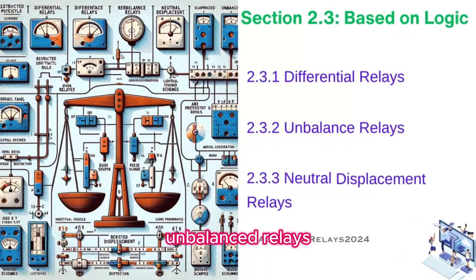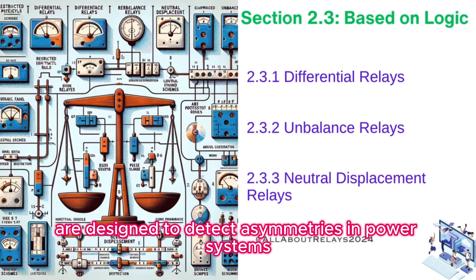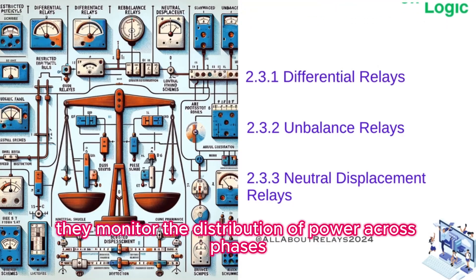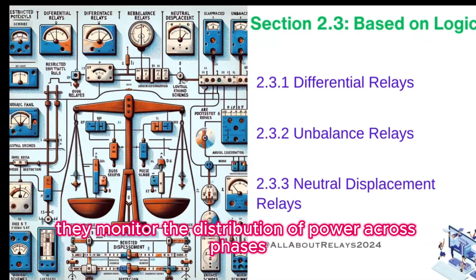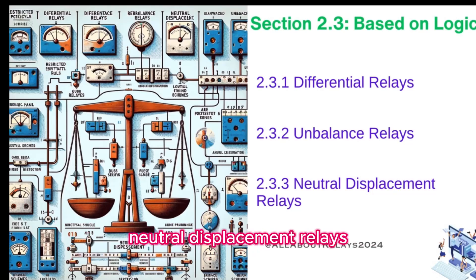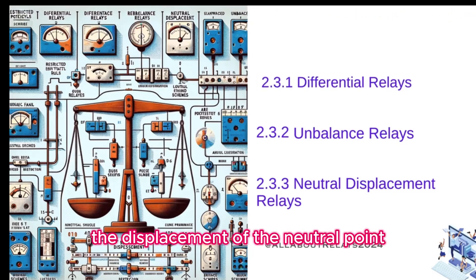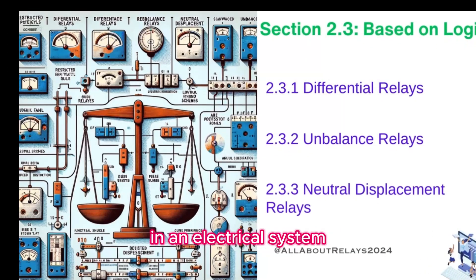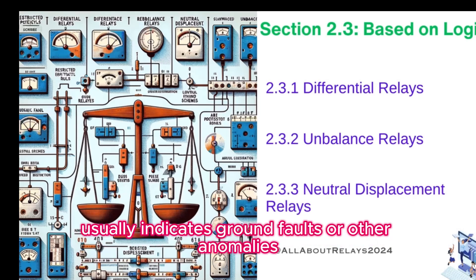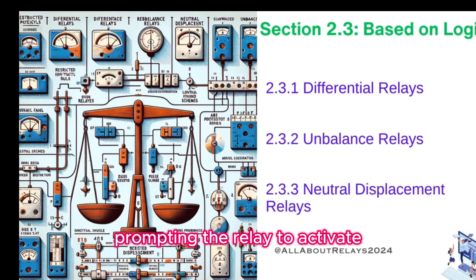Unbalance relays are designed to detect asymmetries in power systems, such as unbalanced loads or phase loss conditions. They monitor the distribution of power across phases and initiate protective actions if an imbalance is detected. Neutral displacement relays monitor the displacement of the neutral point in an electrical system. A significant shift from the normal position usually indicates ground faults or other anomalies, prompting the relay to activate.